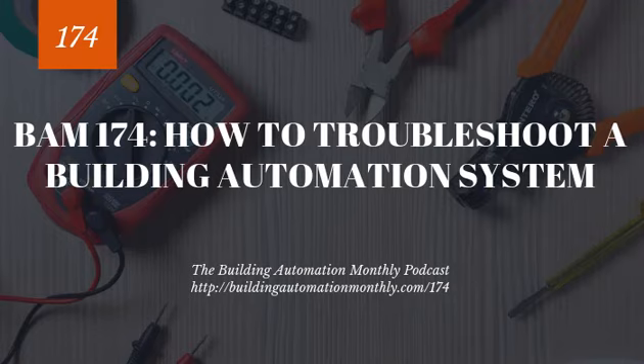All right, so with that being said, what are these two troubleshooting techniques that I'm talking about? Well, they're actually really simple techniques. One is called input to output. Essentially what you do in this technique is that you start with the input and you work to the output. So for example, if you're troubleshooting a space temp issue, you start with the space temp and then you work to the output that affects that process variable.